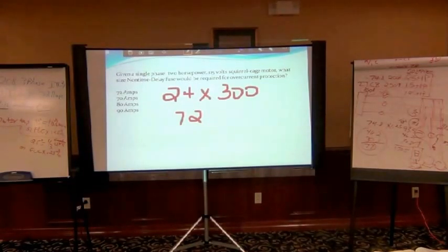So if that same problem says you had initial problems with the starting current, what you're going to do is instead of 24 times 300, you're going to do 24 times what? 400, exactly. And if you multiply that out, that gives you what, 992 something? What does it give you? 24 times 4, yeah, 96. Now, always, no matter what, under exception 2, you have to round down. So you then round that down to a 90.